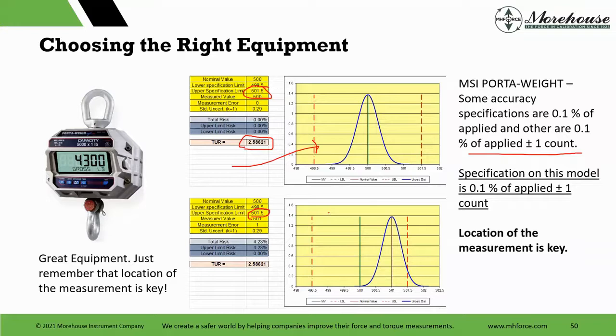Actually, I'm sorry, I messed that up. I had another slide, and that's on me. So I apologize to everybody. This one, we're absolutely just moving the measured value from 500 to 501. And the location of the measurement here is key. Some of them have just one where you could run this through where you have the plus or minus one count and it gives you more room, versus not. This one, we just shifted the location of the measurement. So for this, we just need to be perfect. If it reads anything other than 500, we're probably going to have a problem.